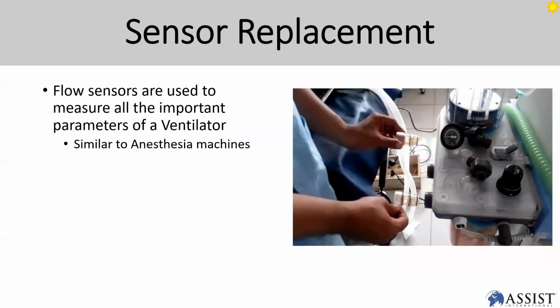So sensor replacement. When you talk about sensor replacement, this is a common thing that you're going to do. If the sensor has failed, you're not going to see any flow reading on your ventilator screen. You need to replace it. You try to calibrate first. If it's not working, you need to replace the flow sensor and make sure to calibrate after that.